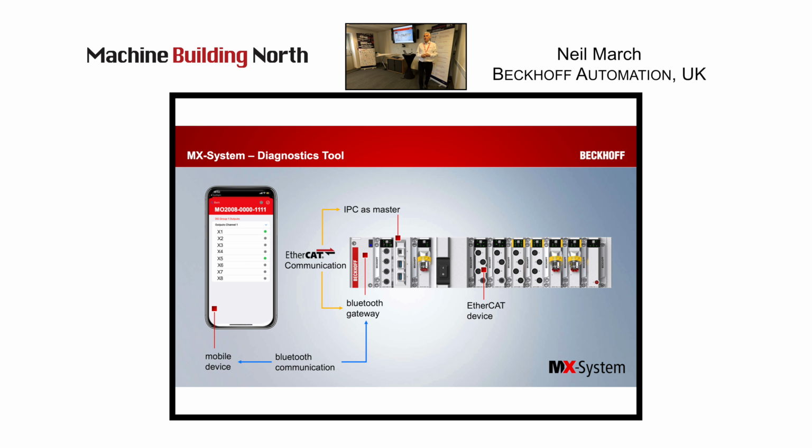Also to that, we have diagnostic tools. This is basically a mobile phone, and it's an app that runs on a mobile phone, and it connects and talks to the actual EtherCAT on the backplane via Bluetooth. And that Bluetooth itself on the EtherCAT backplane is like a node that talks to the PC. So for IT people, the app does not connect to the automation. The app connects to the actual EtherCAT, which connects to the automation.